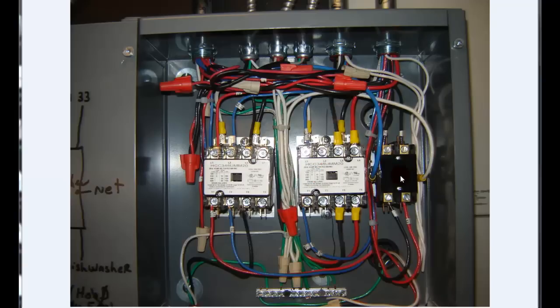So if you have air conditioners or anything like that, if that's supplying air as your main supply, your main make-up air going into the kitchen, then you'd have to shut down the air conditioning system as well. So there's a lot of wiring and a lot of thought that goes into this.